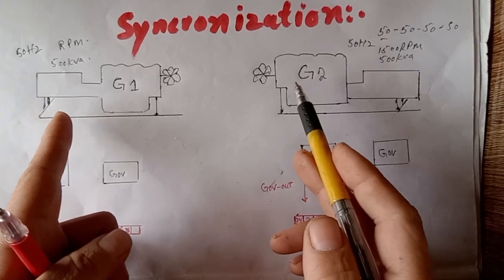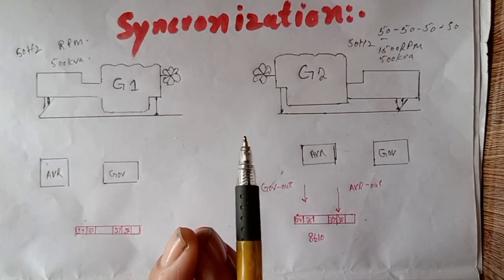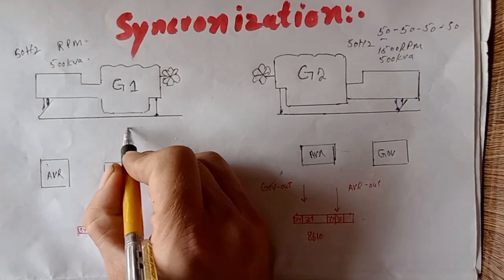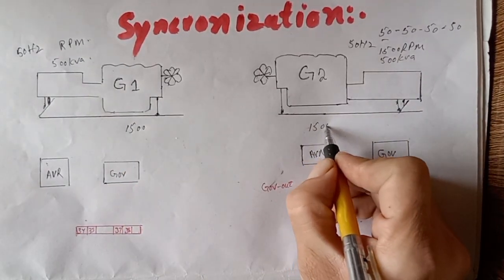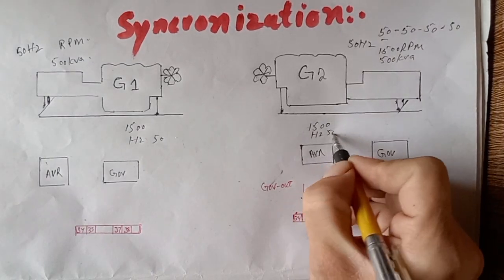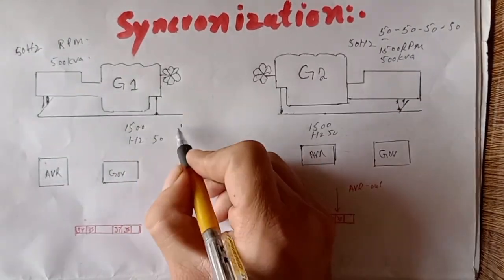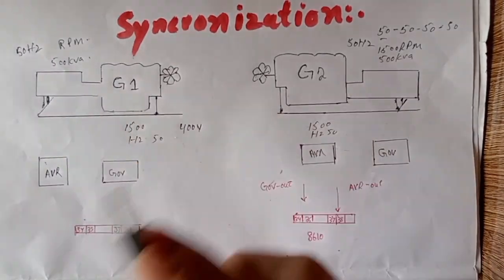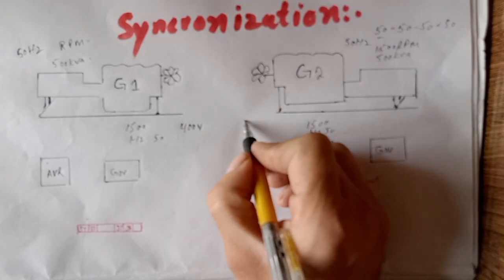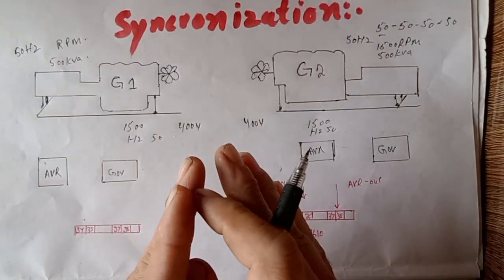Now we have two generators: 500 KVA, 1500 RPM, 50 Hz frequency — now it's easy to synchronize. Fix RPM at 1500 for generator one and generator two. Also fix frequency at 50 Hz for both. One more important thing: same voltage. For example, 400 volts — adjust the voltage of both generators using the AVR or RPM to make 400 V fixed.